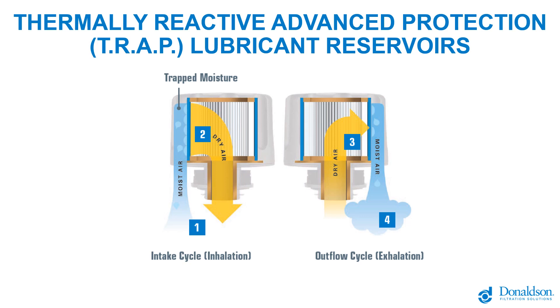TRAP stands for Thermally Reactive Advanced Protection. Here we'll take a look at a TRAP applied to a hydraulic reservoir. As the circuit breathes in air containing moisture vapor and hard particulate — imagine a garbage truck picking up a dumpster — hydraulic fluid moves out to the cylinders to do that work. The fluid leaving the reservoir is replaced by air, and as that air is drawn in, the TRAP breather strips it of moisture and hard particulate down to three microns in size.